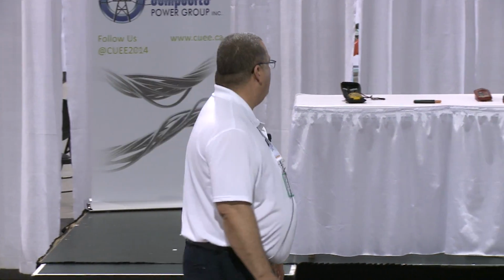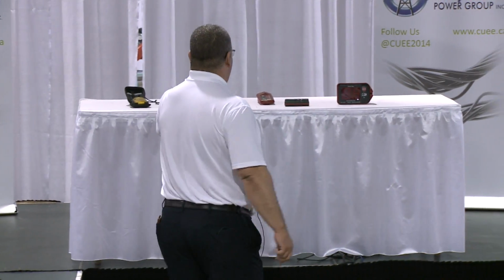Electric fields surround every energized conductor. They are not affected by insulation. What do I mean by that? I've got two different cables here that we commonly use in the industry. I have just a typical secondary wire where what you see is all it has on it is the insulation. The electric field is still present around a cable of this nature.